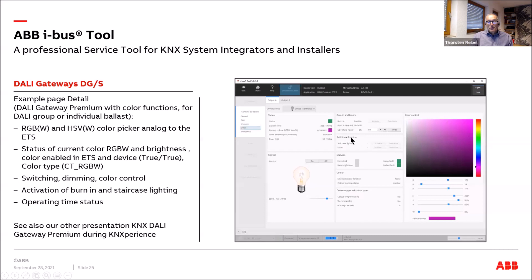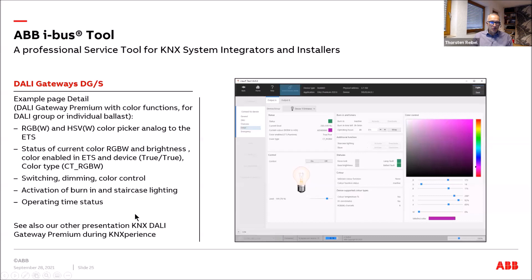For the DALI gateway with color control, a color picker is shown where you can directly select a color and switch the light of a ballast or group on and off to test how the light looks in the room. A slider supports RGB or HSV control principles. You can also dim the light and select which ballast or DALI group to operate. Operating hours are visible here as well.